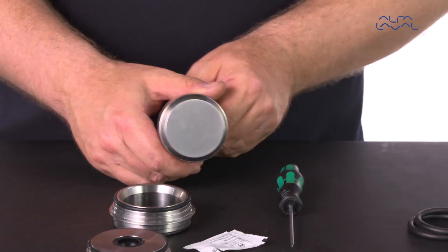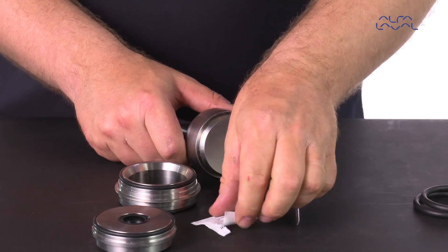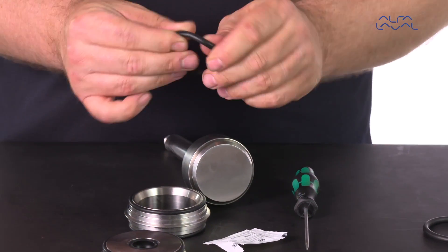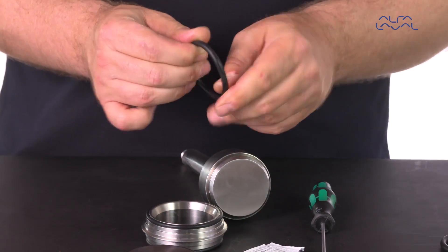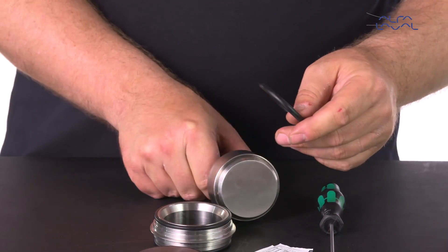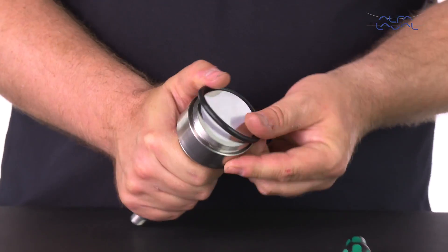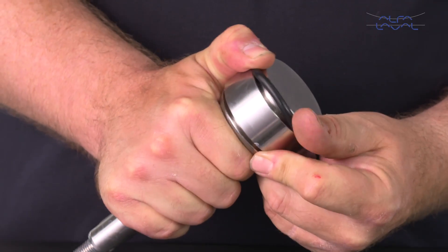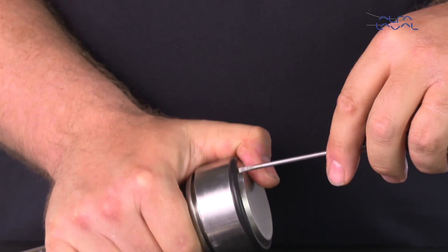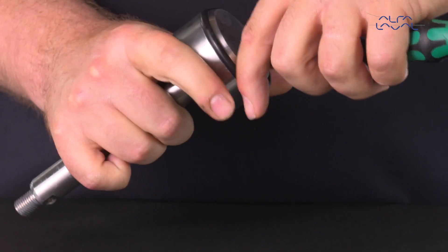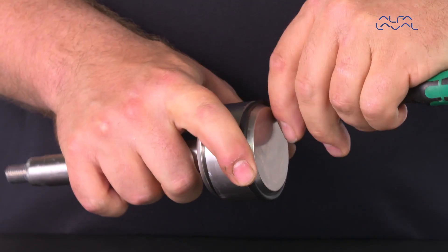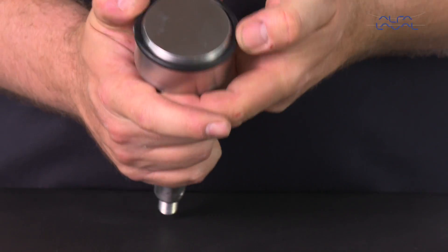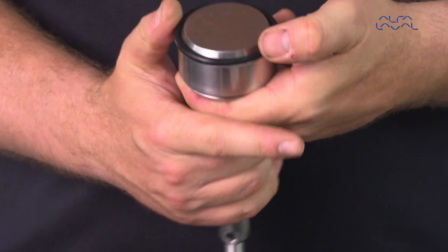Lubricate and pre-mount the plug seals onto the seal groove. Make sure that the seals did not twist or roll during pre-mounting by running a small screwdriver 360 degrees along the backside. Then press the plug seal into the groove using opposite pressure points.